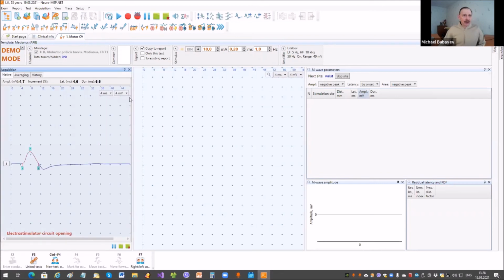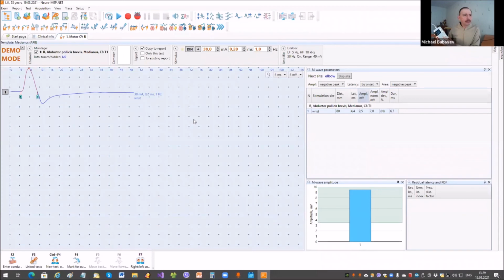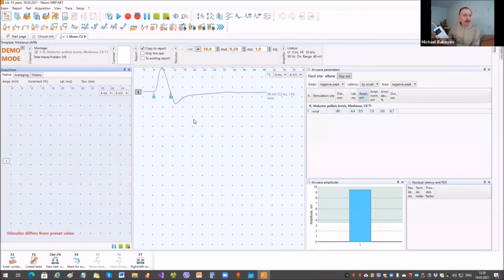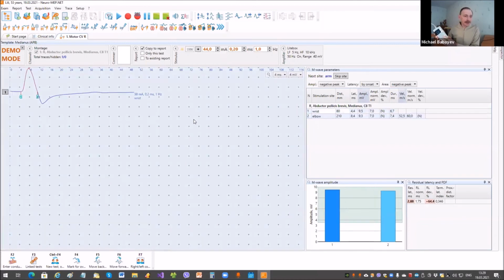I start acquisition here. Then I can change the stimulus intensity. I can do it with the device, only rotating the knob. I rotate the knob. As you can see, the amplitude of the response becomes higher. Then you click OK to put this response into analysis. Then I start another stimulation from the device. OK. Also, I can change stimulus intensity and then save it into analysis.